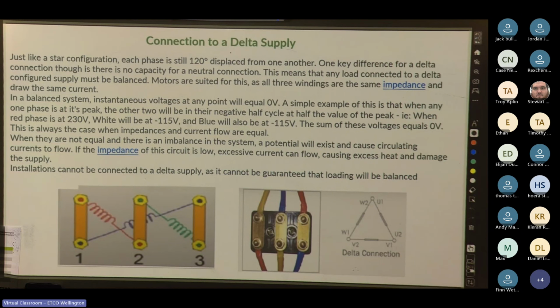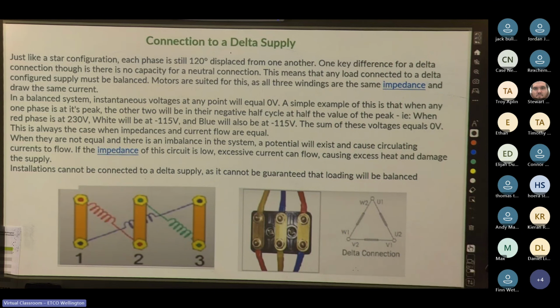This is the case when impedances and current flows are equal, but obviously they're not always going to be. When they're not equal and there is an imbalance in the system, a potential can exist and cause circulating currents to flow. If the impedance of the circuit is low, excessive current can flow, causing excess heat and damage to the supply. Installations cannot be connected to a delta supply as it cannot be guaranteed that loading will be balanced. So it is very rare that you will ever see a mains connection in delta, simply because we cannot control whether the load will be balanced at any one time. So we still need a neutral point for that current to flow back to the other phases.